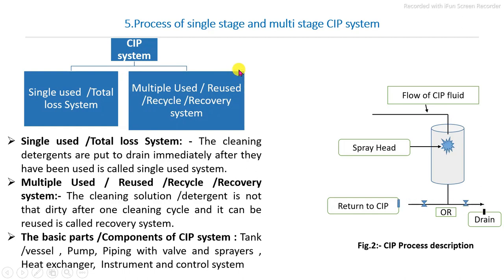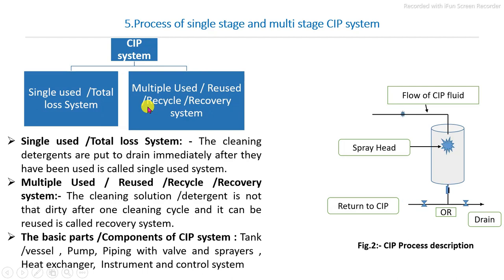The CIP system mainly involves two groups. The first is the single-use total loss system, and the second is the multiple-use, reuse, or recycle system. In small-scale industries or single processing lines, the single-use total loss system is used, which has low investment but very high processing cost. For aseptic plants and beverage and dairy processing plants, the multiple-use system with reuse and recycling is mostly used.